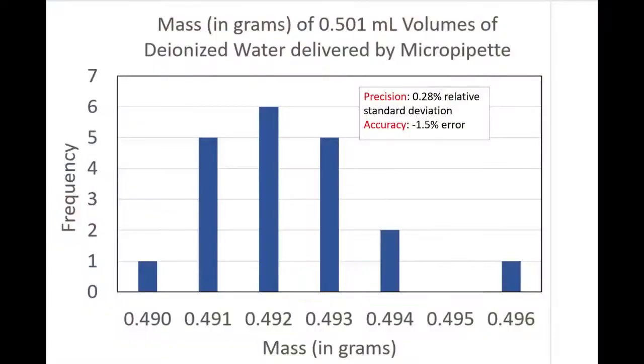To illustrate the high precision and accuracy possible with the micropipette, the mass of 0.501 milliliter volumes of room temperature deionized water was measured 20 times. The measurements show a relative standard deviation of less than 0.3% and a negative 1.5% error based upon the density of water. The accuracy of the micropipette may be improved with its periodic recalibration.